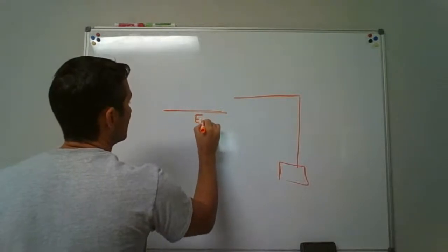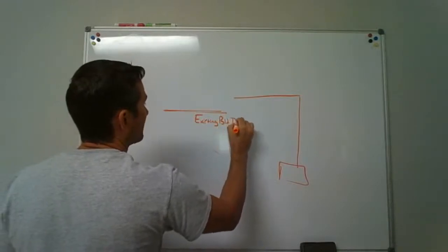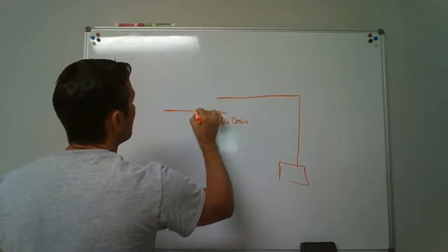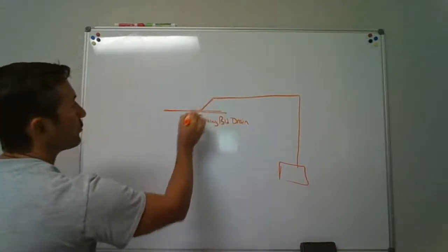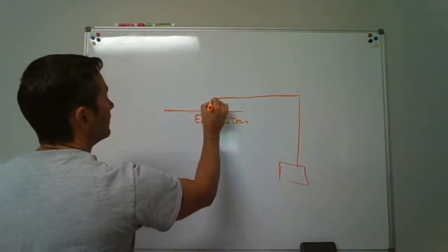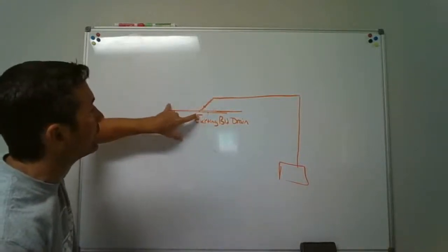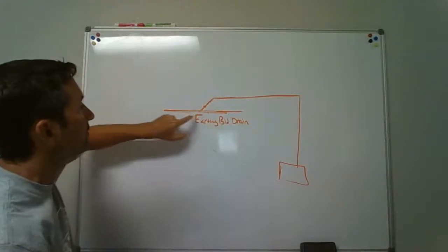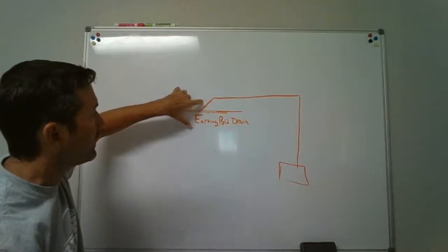This is the existing drainage. Let's just say it's the existing building drain. We're going to come across, and then we're going to come off the top of this with a Y fitting. So through a Y fitting, dumping into the top of the existing. Okay, so there's our fitting. Y fitting, we could straighten it back up with a 45. This needs to be pressure rated because that's part of the pressure rated line. We can glue into a regular 3x2 fitting here, and this can all be cellular foam core pipe. This all has to be pressure rated pipe connected through a Y fitting into the top.